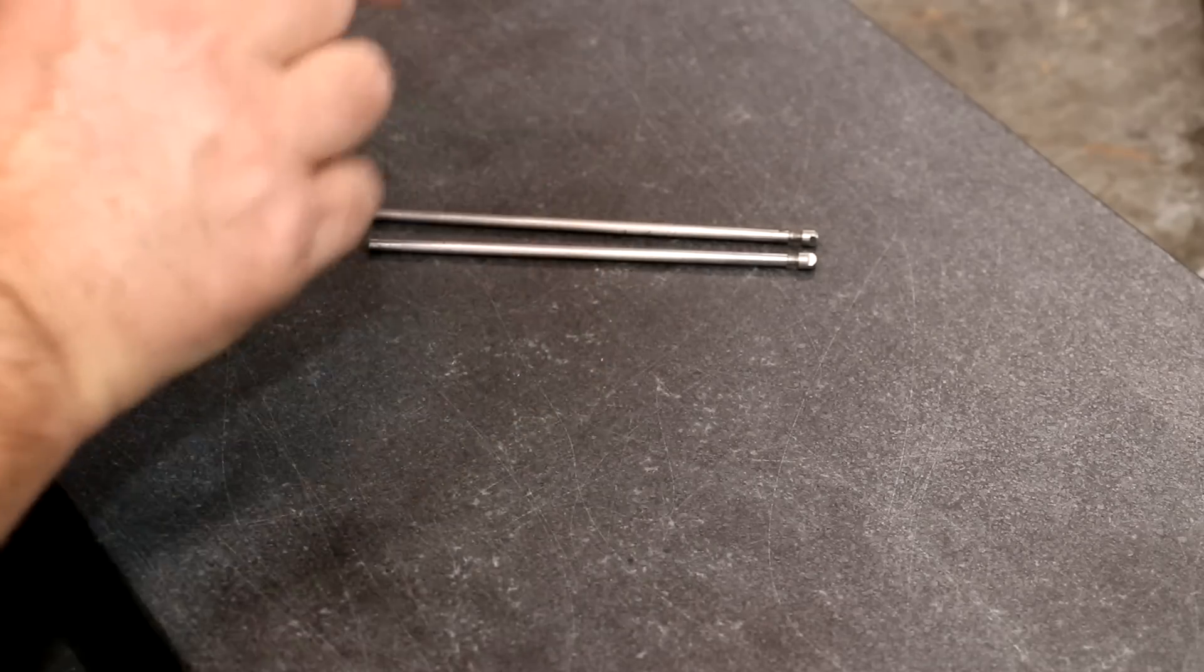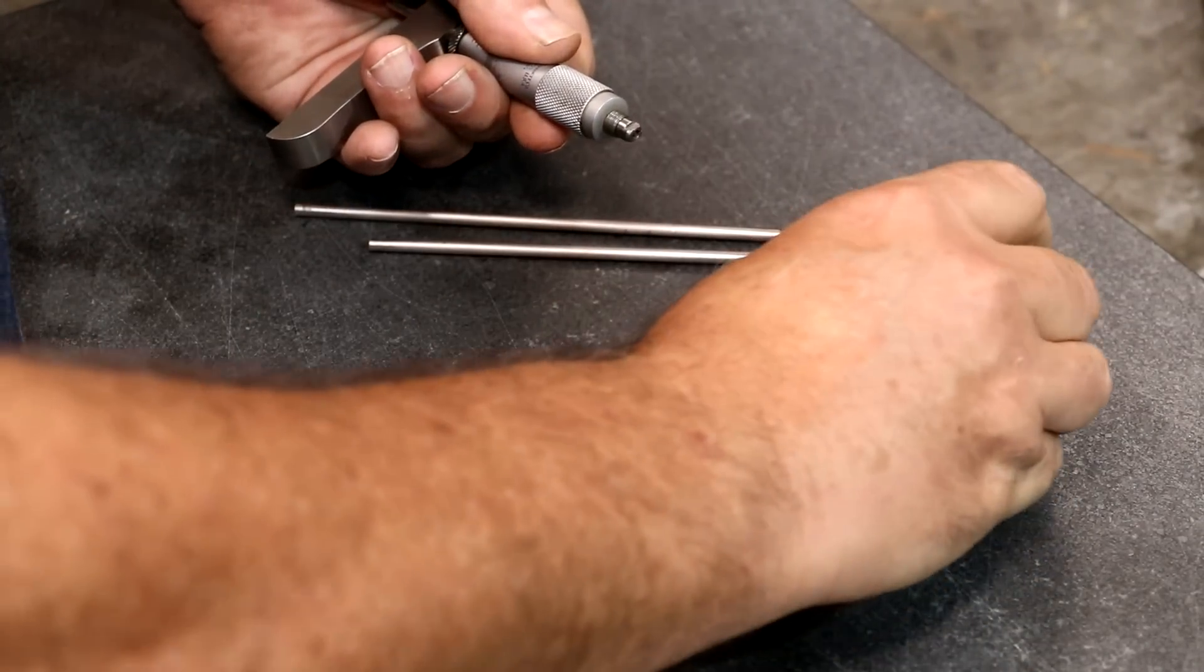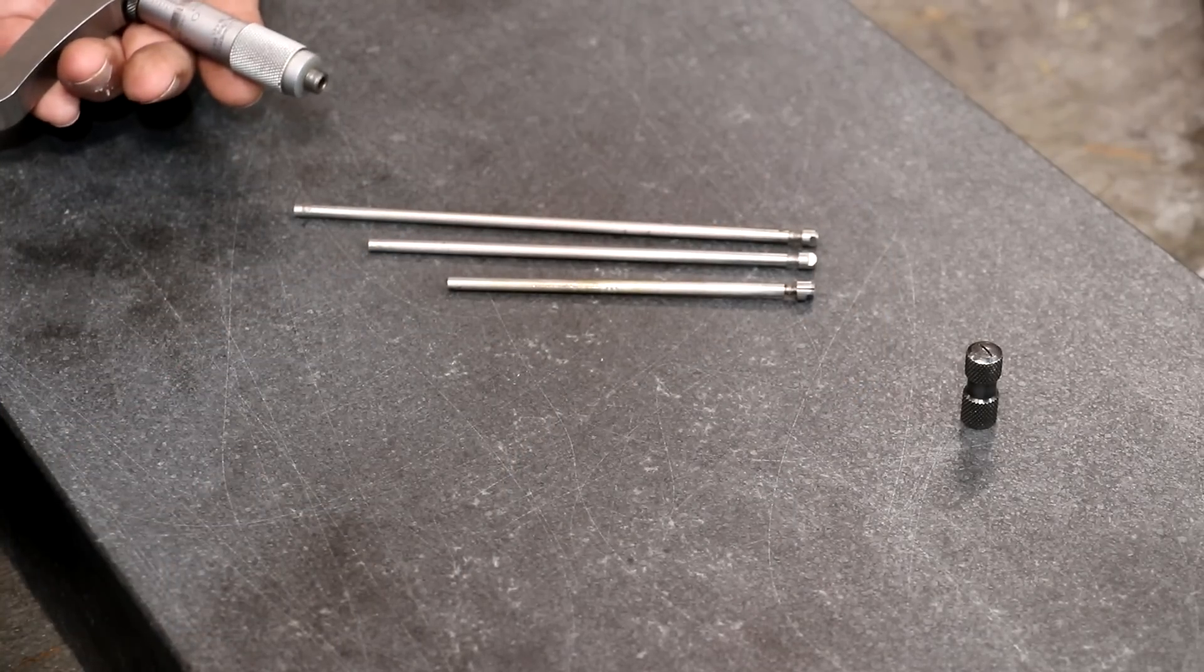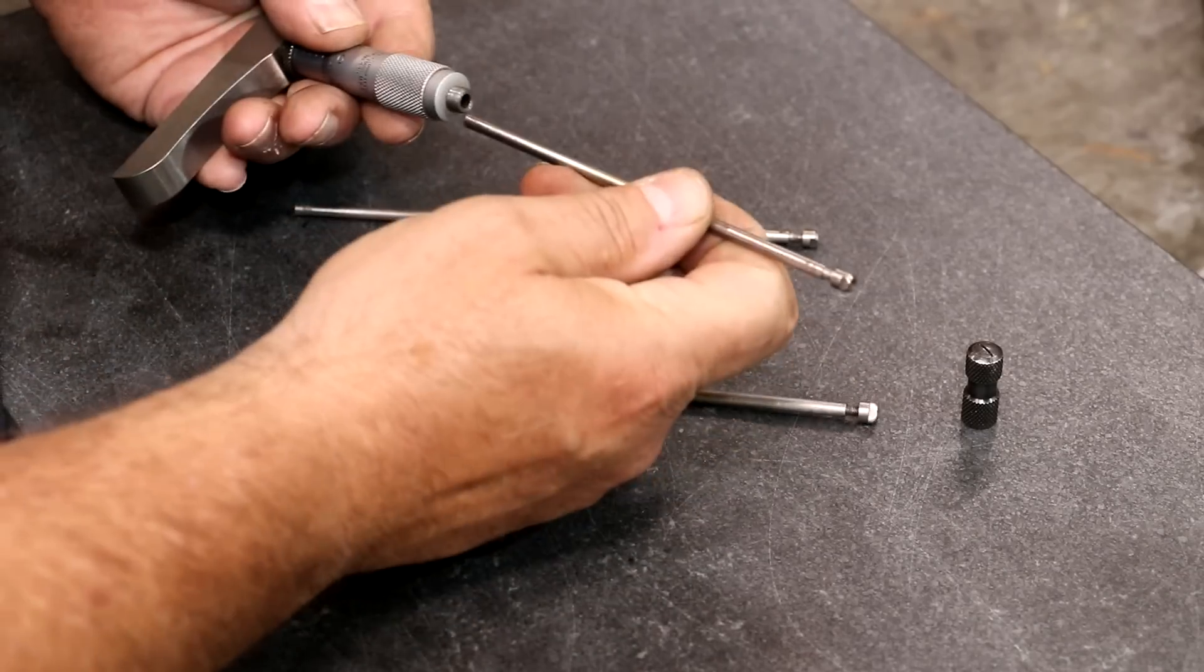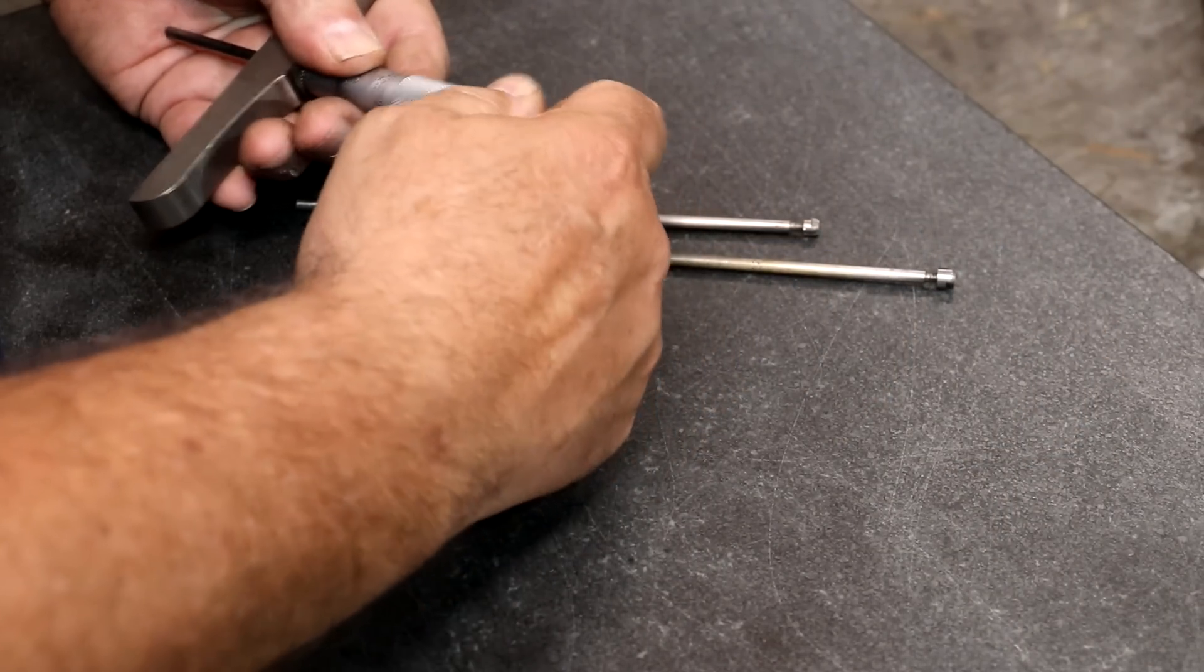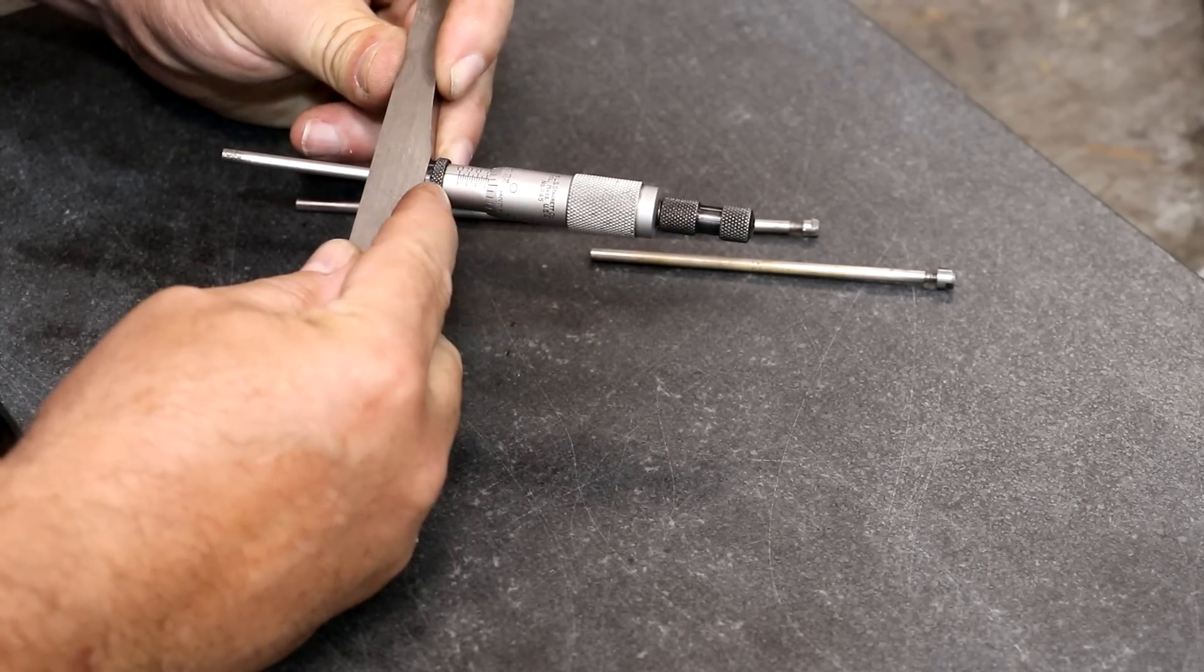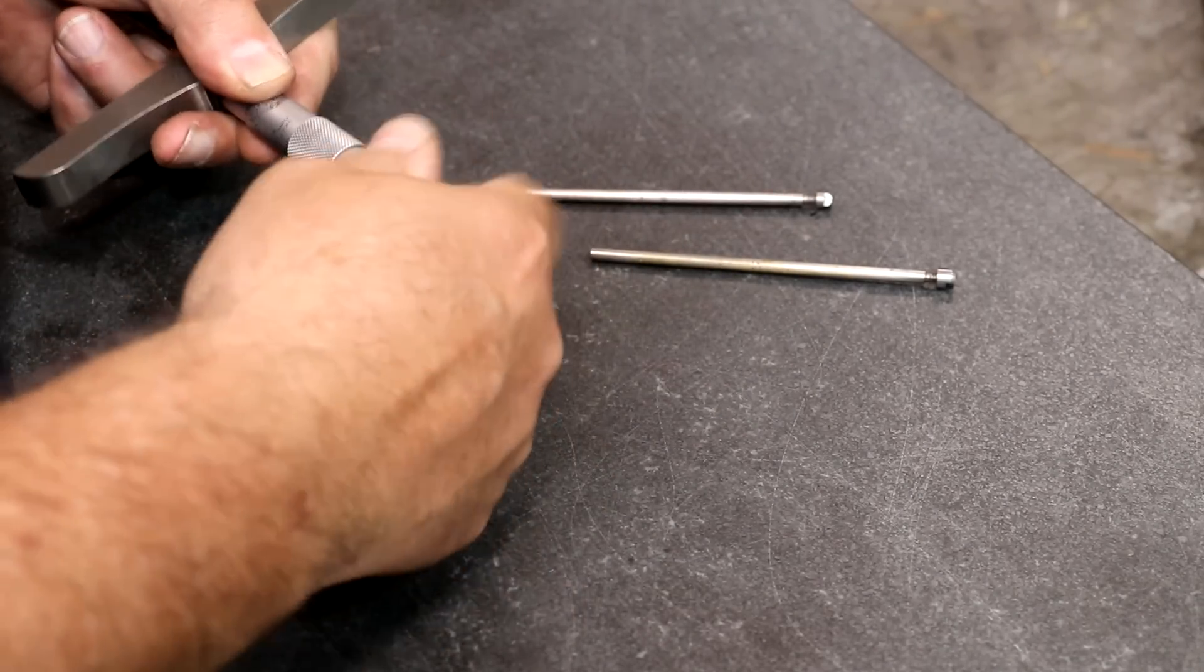The nice thing about these is these rods are interchangeable and you can take them out and use them as needed. And let's talk about first, how do you do that? So there's a little thimble up on the top of this that unscrews. And when you do, your rods just come out of there. So there are my three rods that come with this. If I was going to measure something between one and two inches, I would then take this rod, put it in there, and then I would screw my top on. And now I've got a range when I'm reading this number from zero to one, this is going to be between one inch and two inches with this rod, two and three. So alright, let's start with the easy. Let's go back to our zero to one inch set here.